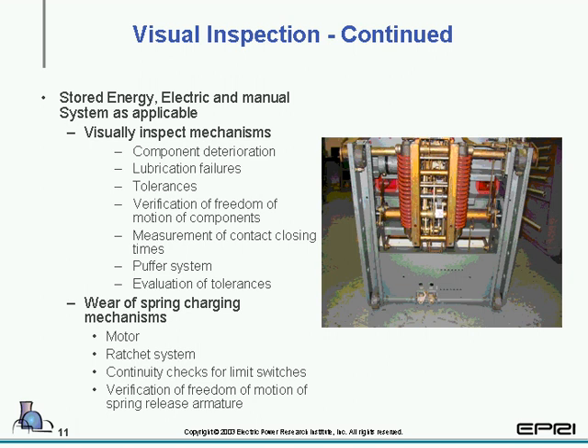Next one we're going to take a look at, it should be on your screen, is the stored energy, electrically or manually system, as applicable. The general idea on this one is that you're going to want to take a look at the operating mechanism. Some of these items on there you cannot check physically. You must actually operate to verify that it works correctly, such as the puffer system. The operating mechanism actually operates that, so it's actually part of it. And then you're going to want to take a look at wear of spring charging mechanisms, the motor. We also have the racking system as well, if it has any interlocks that connect with the breaker, and limit switches.